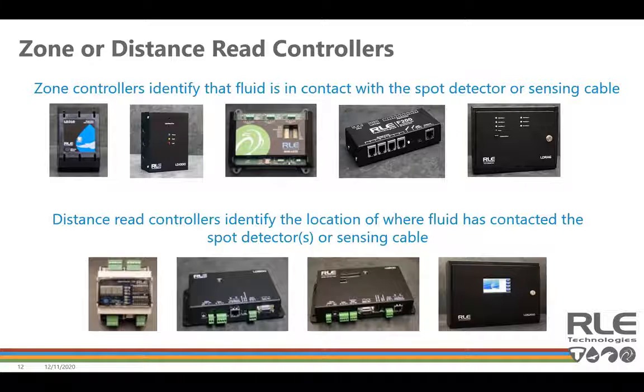Along with spot detectors and/or sensing cable, which again is what's going to detect the leak, you will need a leak detection controller to notify you of the leak. Our controllers can operate as standalone devices, or they can tie seamlessly into an existing building automation or network management system. The communication protocols available for some of our controllers are SNMP, BACnet, and Modbus. And we do have a product matrix available to help you choose a controller that's best suited for your application.